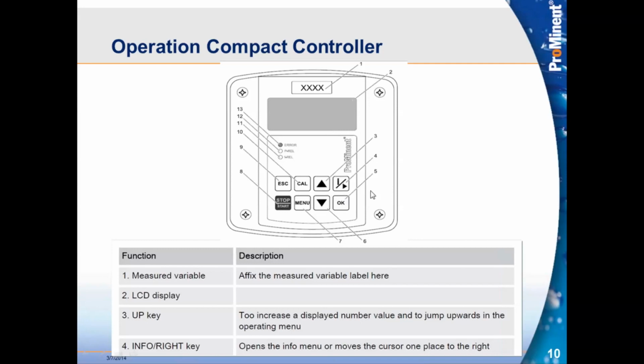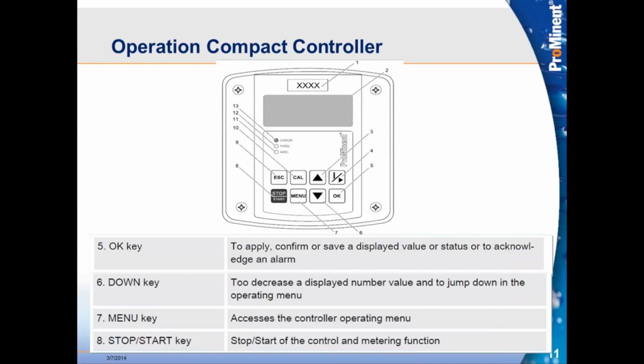To the right here, we're seeing more and more, it's kind of the new way that we're doing it. We have an information and a right arrow key. So information, you can toggle between what's being displayed without interrupting the operation of the unit. Likewise, if we are adjusting a parameter in the unit, maybe doing a calibration, we go to the next digit to the right by pressing that same button during that process. So that's that information right arrow button.